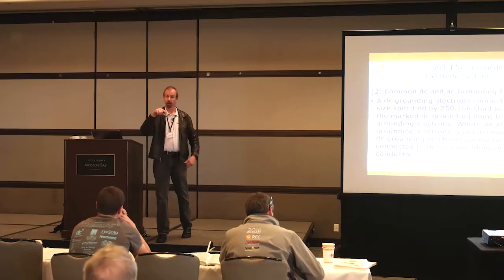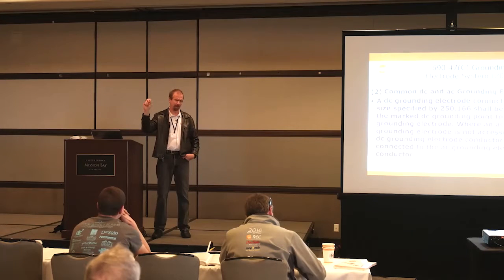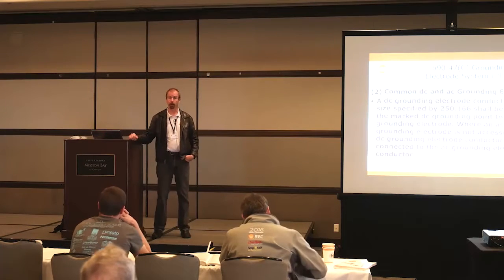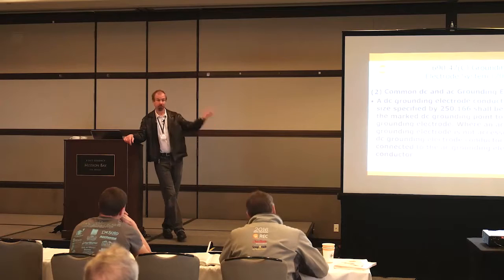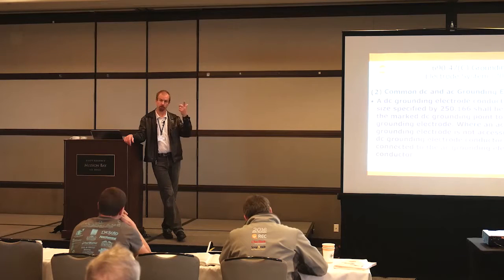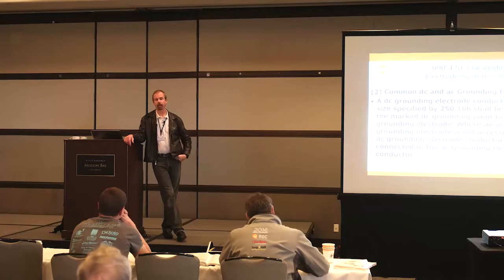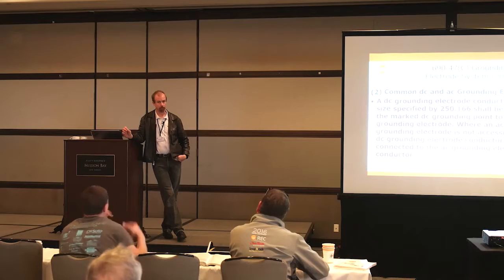Okay, so if it's not 8 feet in the ground, let's say it's 4 feet or 5 feet in the ground, now I'm going to have a driven ground rod, and I'm going to take a grounding electrode conductor, and I'm not going to take it to the frames of my panels, which is the way it's written in 47D. I'm going to take it to whatever's the easiest way to connect to the equipment grounding conductor. If it's a bare copper wire, so let's say I ran a bare copper wire for my equipment grounding conductor in my array, okay, fine. All I need is a split bolt, connect the number 6 to that and go on down. Because anywhere on the equipment grounding conductor and anywhere on the frames are all bonded together, because they're all one electrical unit, and I can connect that to the grounding electrode.